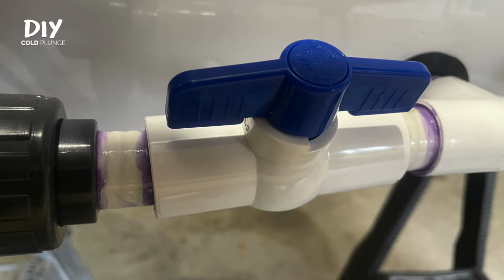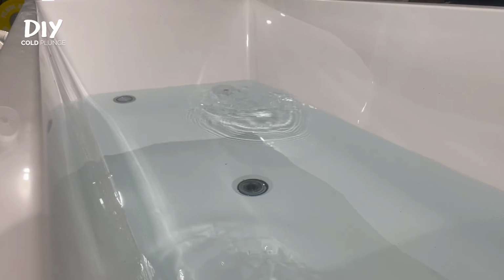During a leak test, I recommend filling water just above the return line on your tank. Beyond that, you don't need to fill it anymore, but we need to make sure that we're testing the return fitting for leaks. Now that everything is connected, you have water in the tank, and your ball valves are all pointing in the right direction, it's time to turn your pump on to actually do the leak test.